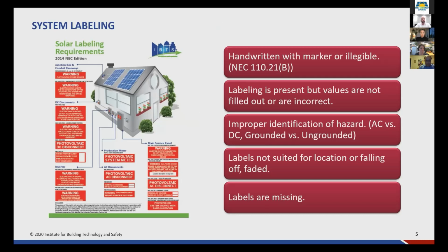When we're looking at these panels, there's thousands of panels in a system, 2 wires per panel, and they connect to some trunk lines that ultimately create raceway back to the distribution. So with that much customization, or that much component available in your system, it's no wonder that ends up being the bigger issue on site. Again, labeling occurs most often, but I won't say it's not a safety consideration.